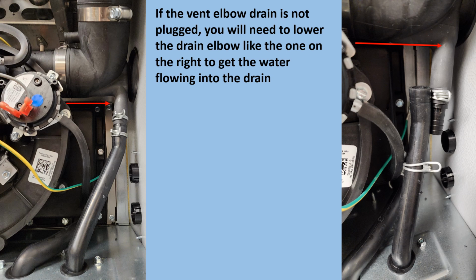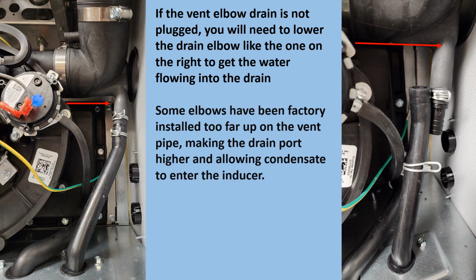As you see, the one on the left is more level, and the drain over on here you see is pitch drop down on the nipple end, so that you notice that now you have a little slack in your drain tube there. But we'll go to that. Some elbows have been factory installed too far up on the vent pipe, making the drain port higher and allowing condensate to enter the inducer.